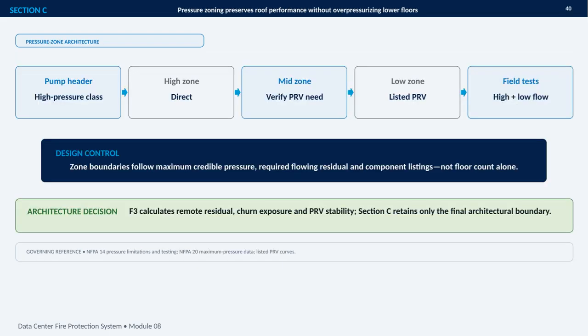This slide presents the pressure zone architecture used to protect system performance across different elevations. The pump header supplies the system, but the building is divided into high, mid, and low pressure zones so that the upper areas receive the pressure they need without overpressurizing equipment and piping on the lower floors.